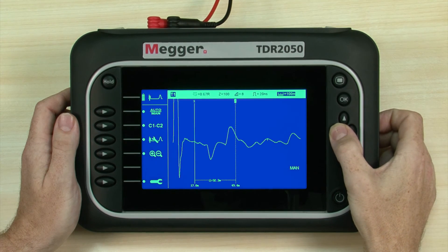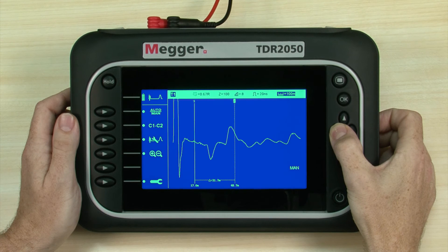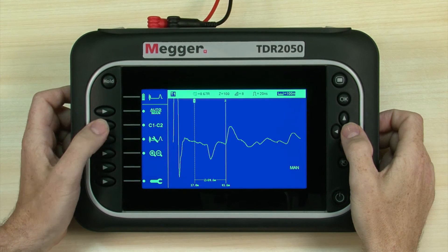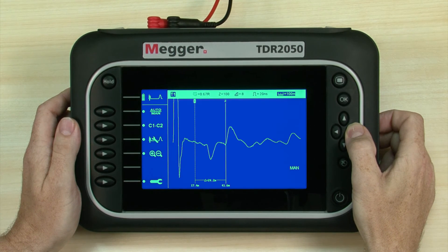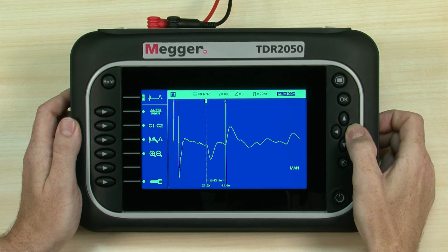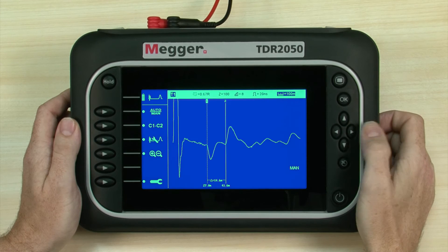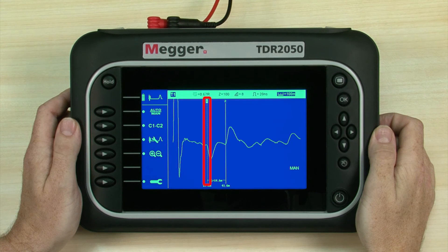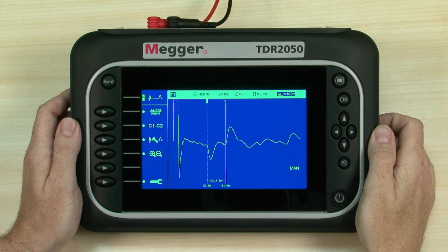The C1, C2 soft key toggles the active cursor, which changes to a dotted line. Press the left and right navigation buttons to move the selected cursor. For extended distances, hold the navigation button down. Its travel will accelerate after a second or two. Release the navigation button to stop cursor movement. We position cursor 1 at the start of the first event and cursor 2 at the start of the second. A delta measurement shows the distance between the events.